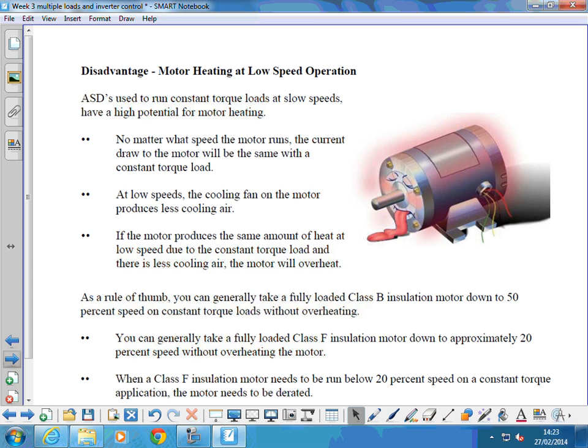Okay. Motor heating at low speed operation. ASDs used to run constant torque loads at low speed have a high potential for motor overheating. No matter what speed the motor runs, the current drawn by the motor will be the same with a constant torque load. Yeah. So if you're running it slow, these induction motors are usually cooled by a fan on the end of the shaft. So if it's running slow, that fan's not pushing so much air through the motor, and therefore it's going to get hotter than it normally would.